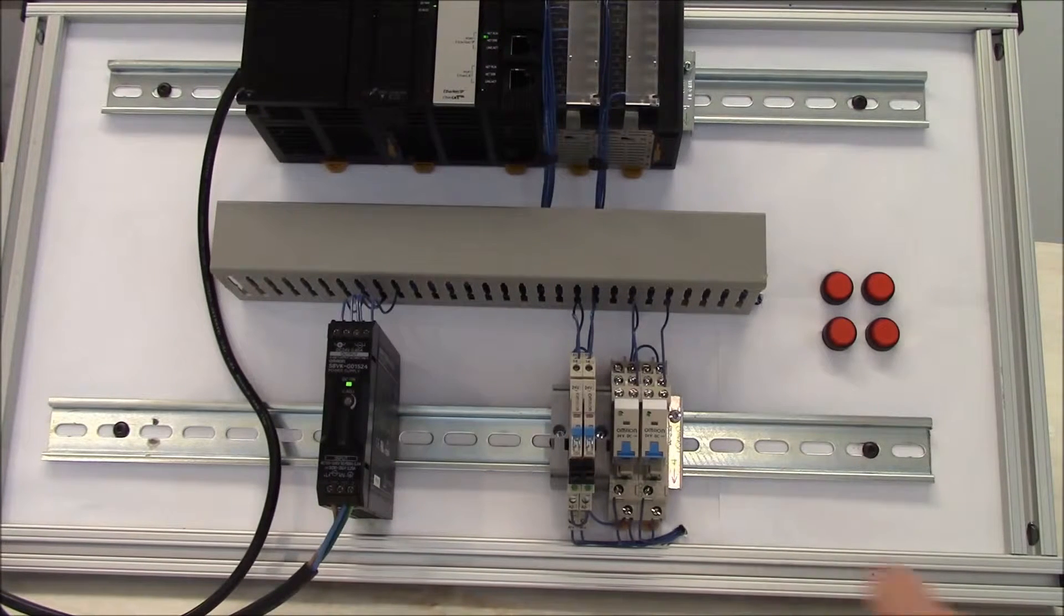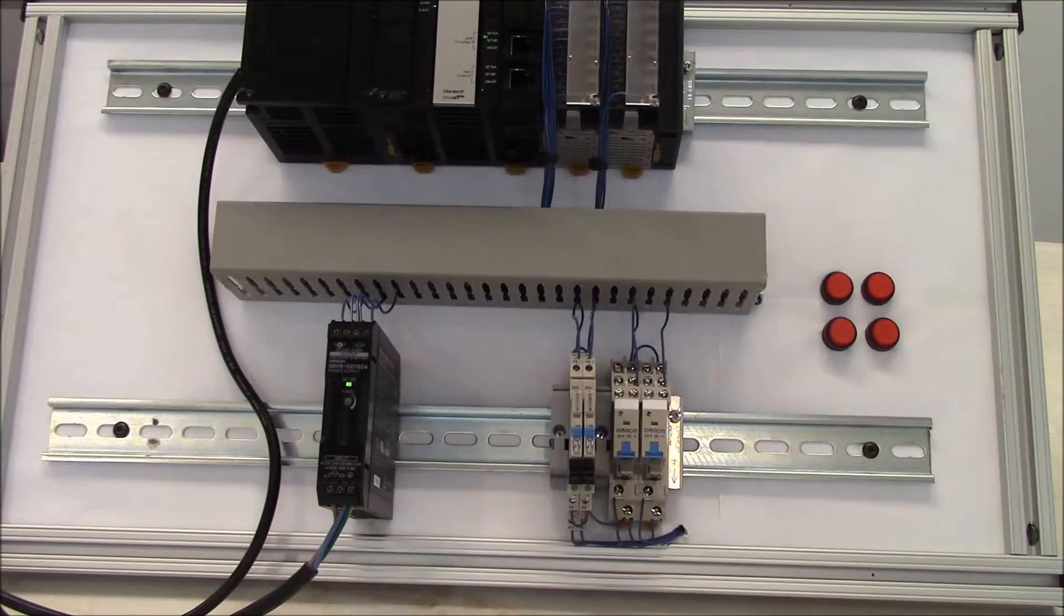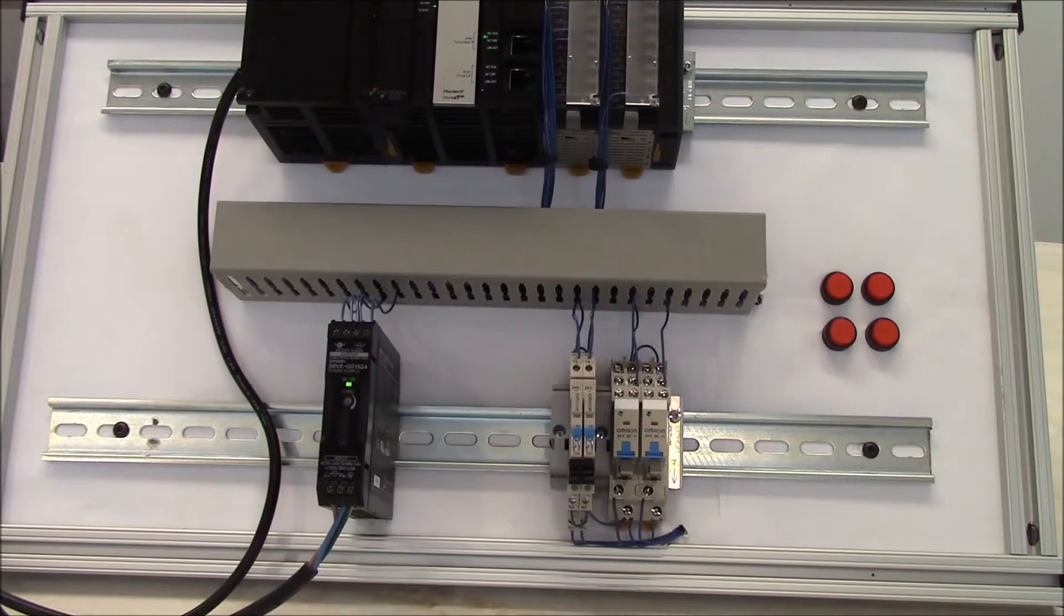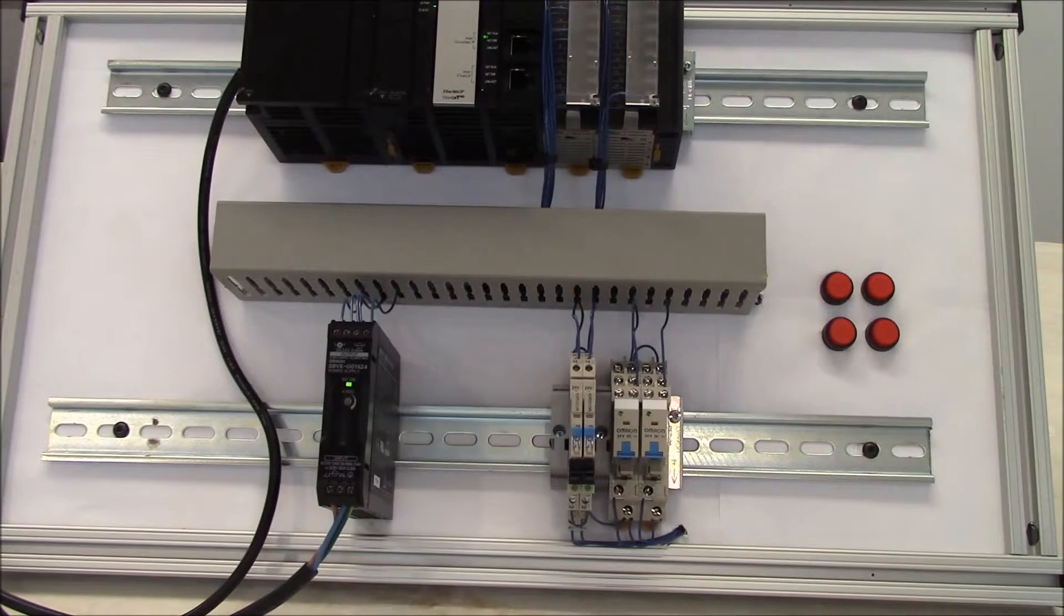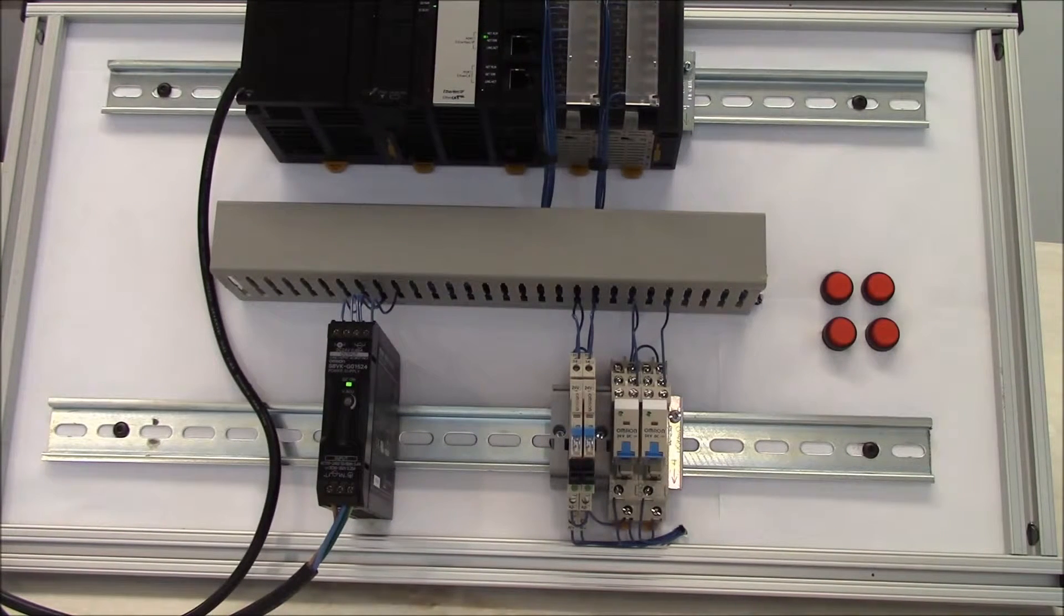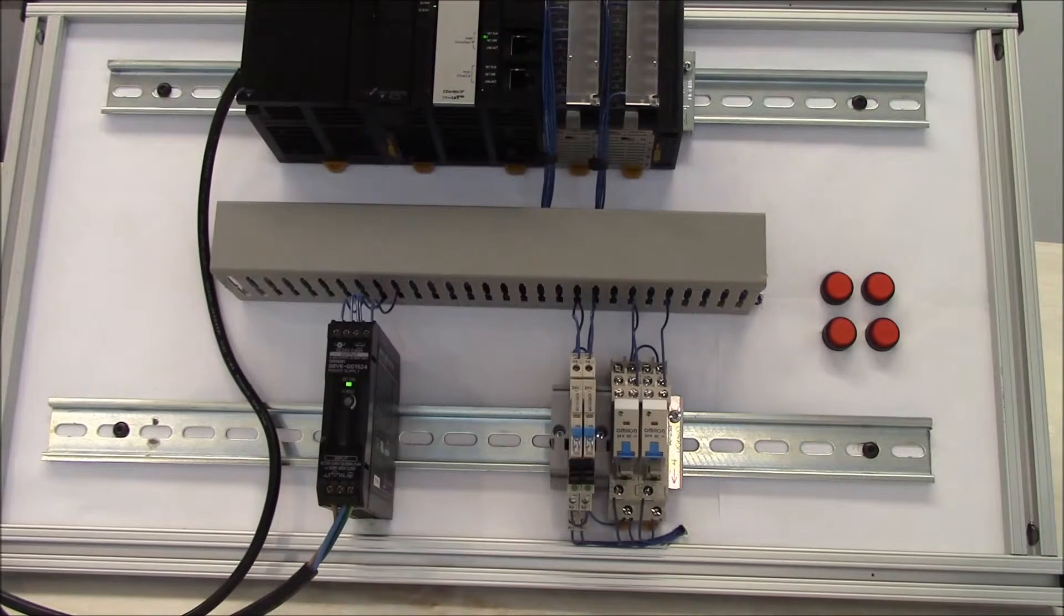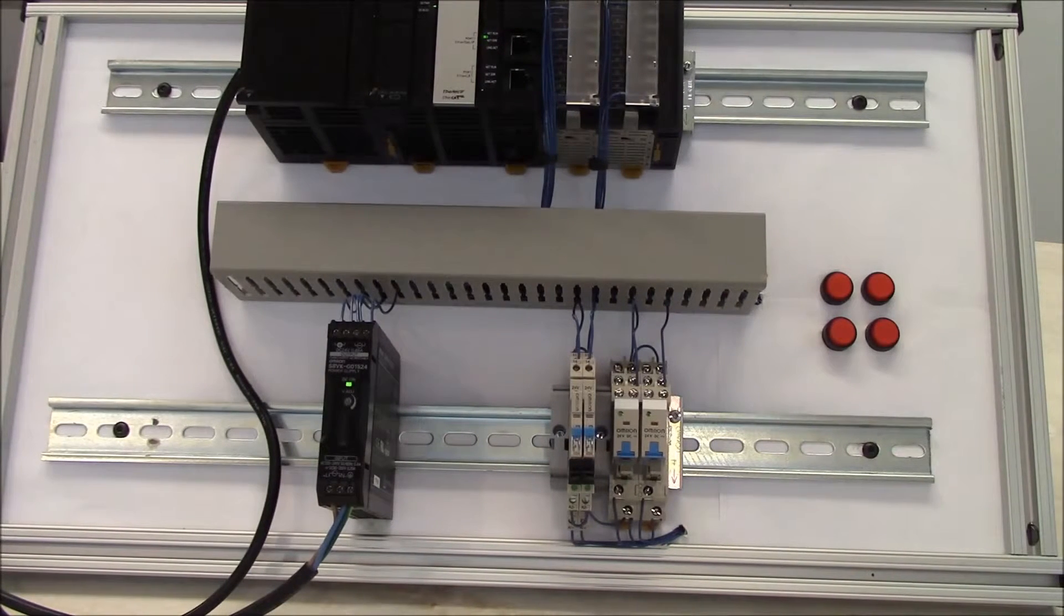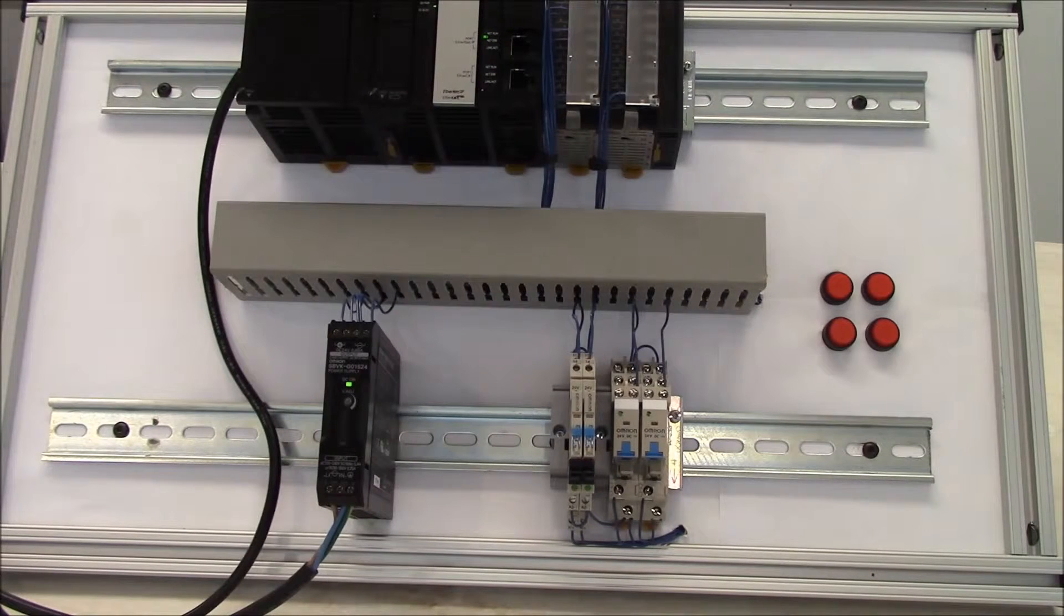On the G2RS, we offer a single pole double throw. It has a 10 amp contact rating and you can get anywhere between 100,000 to 700,000 electrical operations depending on the current you're running.